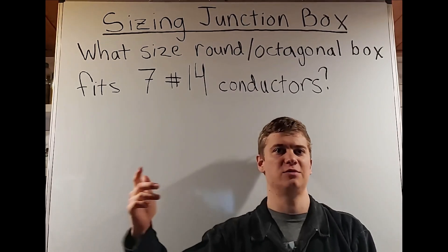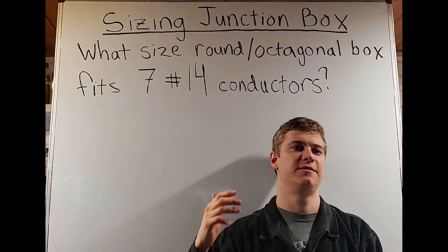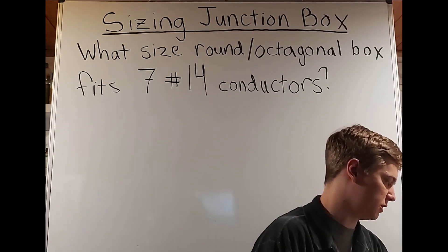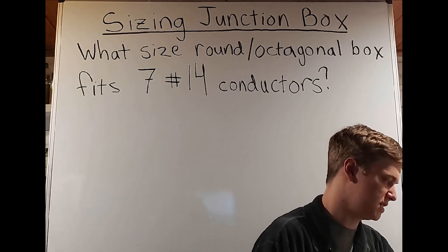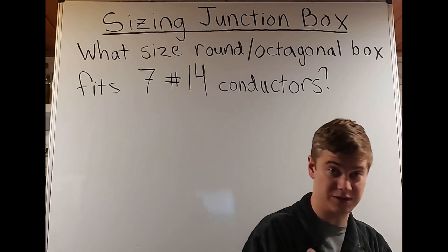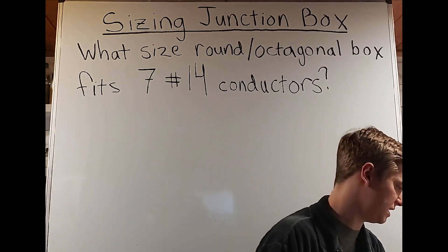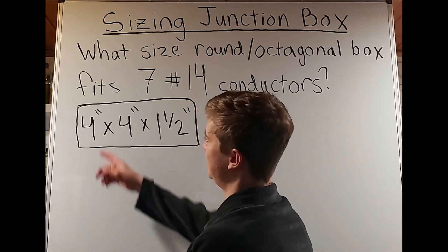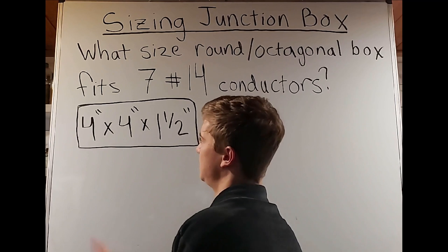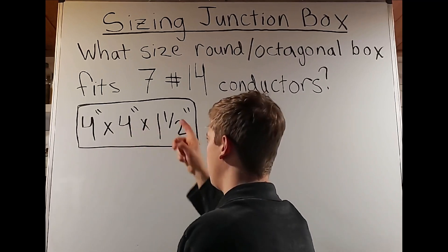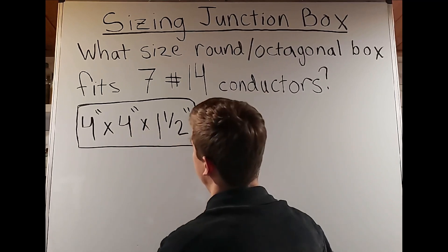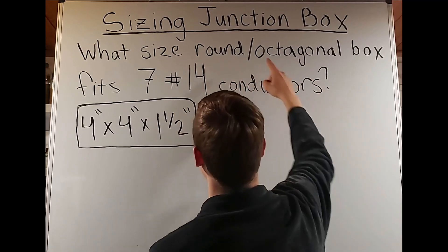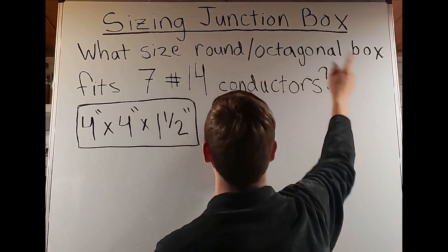Next question: what size round/octagonal box fits seven number-14 conductors? Looking again at the round/octagonal section, this time under number-14, we see the number seven, and we see that is a four by one-and-a-half inch. Just like before, the first number is doubled — so we have a four by four by one-and-a-half inch box that can fit seven number-14 conductors in a round/octagonal box.